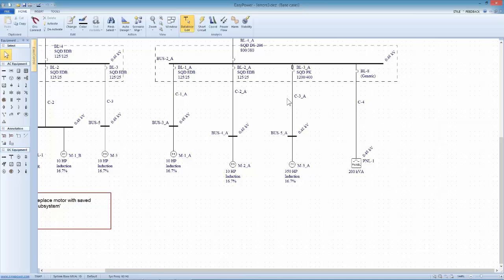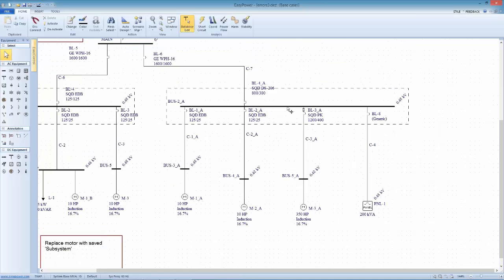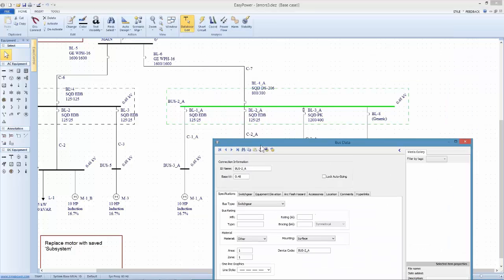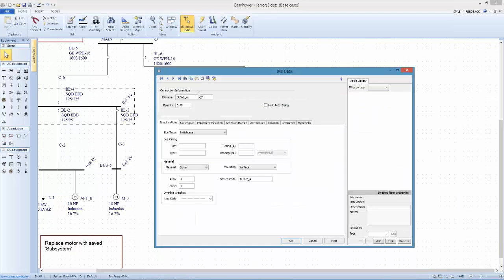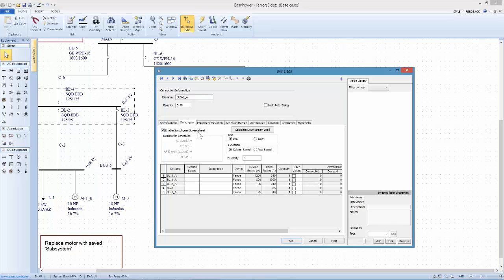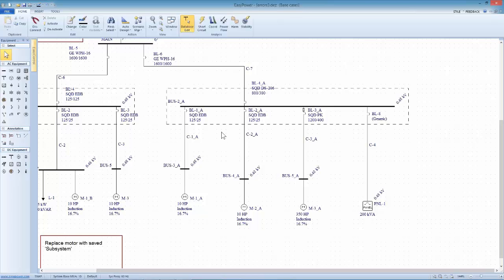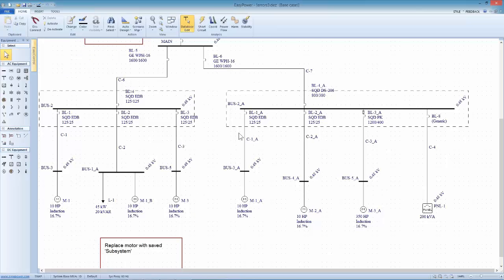Okay, so that applies even when I've drawn a bus as a discrete, standalone bus. One of the trade-offs is I probably need to do the entry here because I haven't described a specific manufacturer. And again, this goes to the equipment duty rating for this type of equipment. I can also enable the switchgear spreadsheet, which will allow me to do a downstream calculation here, and it does the comparison based upon which is designated as the main for this bus as well. Okay, so those are some properties of the EasyPower features that allow us to check as we go through and verify that we're not making data entry errors along the way.